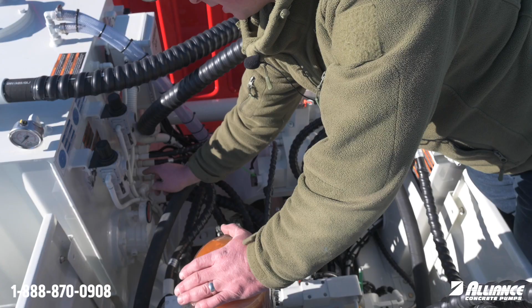There's actually a valve in here. As you thread that filter out, there's a valve in there that actually closes so no oil will leak. So when you go and change the filter, which we have a video on, remove it and then reinstall it. And that's at 100 pump hours. You want to change that. And then after that, you want to do it every 250 after that. So that's that indicator and filter housing right there.